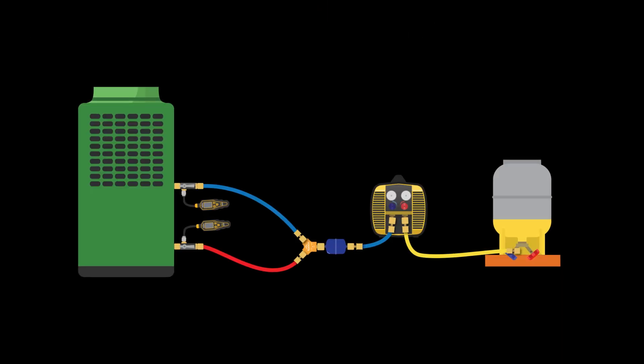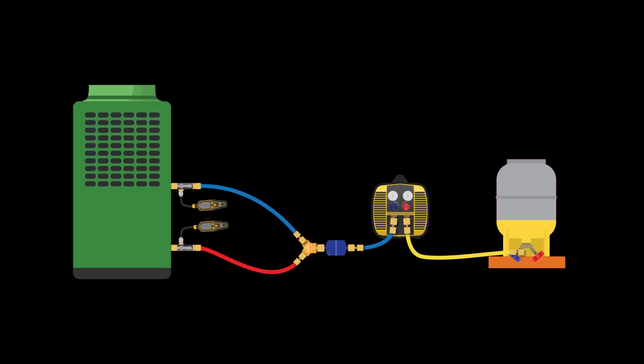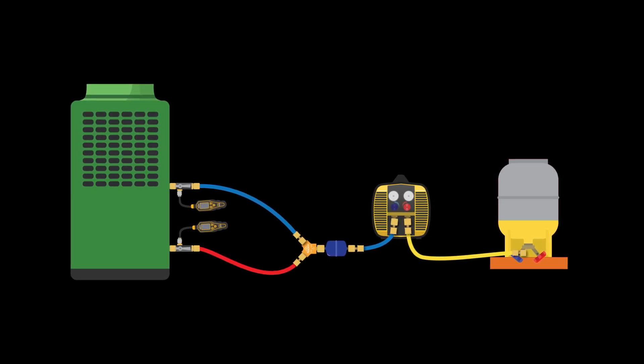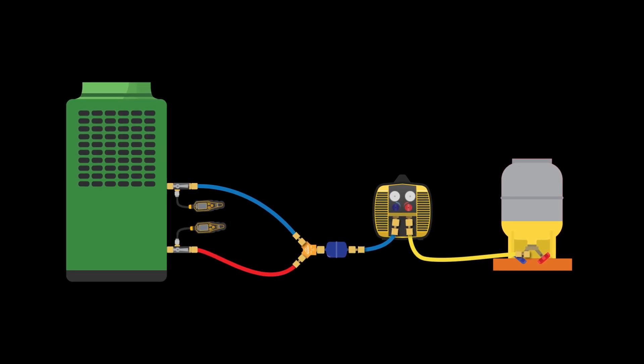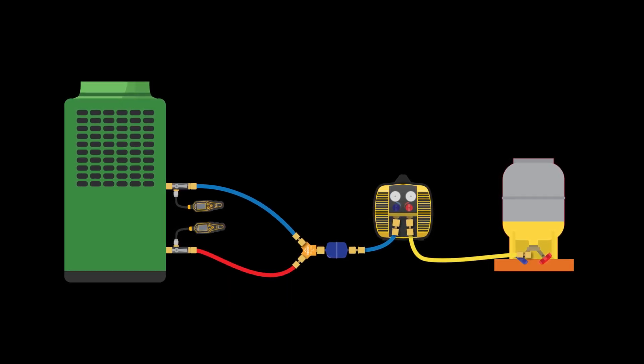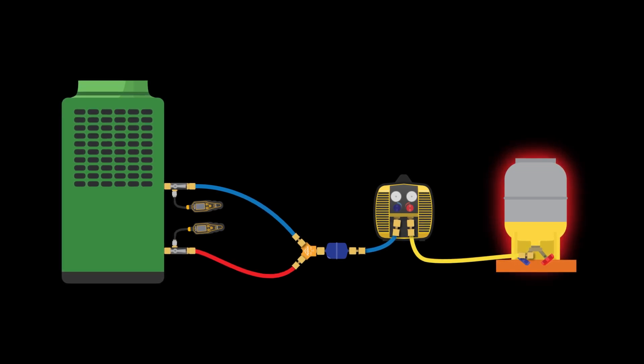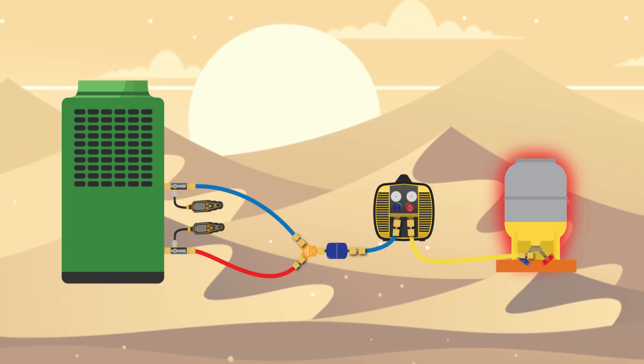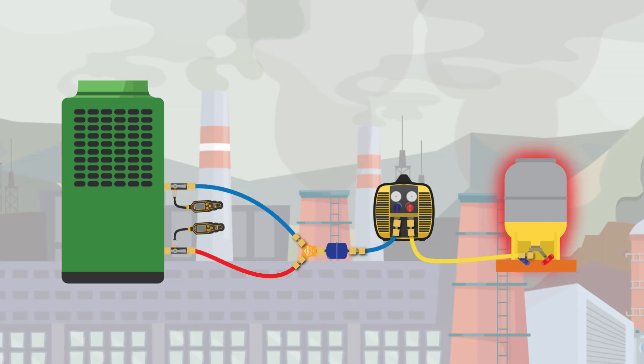Two-port direct refrigerant recovery is the most commonly deployed refrigerant recovery method. While valued for its ease of setup, it does have some limitations. The most common drawback is heat buildup at the recovery cylinder. This heat buildup can often be eliminated by deploying the full-flow techniques discussed earlier in this video series. However, in some environments with high ambient temperatures, other techniques or add-on tools should be utilized.